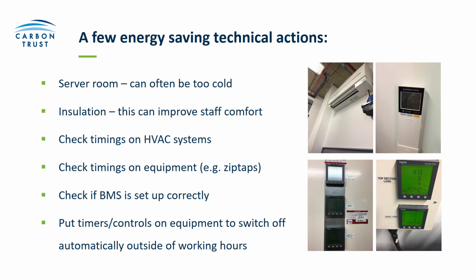If your organisation has a server room, these are often kept really cold because IT teams tend to worry about equipment performance when it's too hot. However, most IT equipment nowadays doesn't need to be kept that cold, and typically they're overcooled. If you can reduce this cooling even a little, you might get some pushback from your IT team, but try reducing it by a couple of degrees. Check for any issues with your technical equipment, and if there are none, keep increasing that temperature.